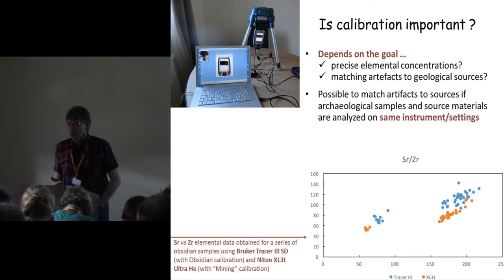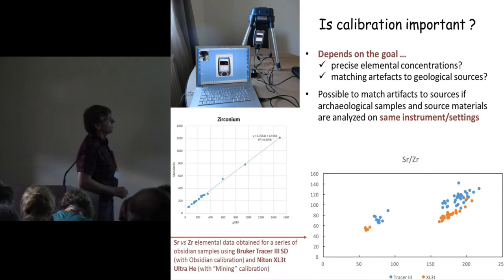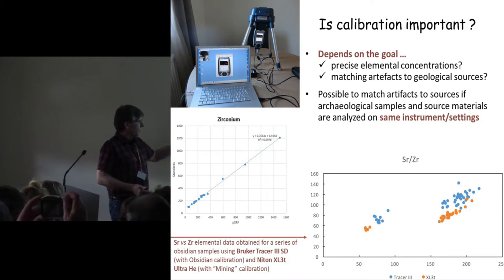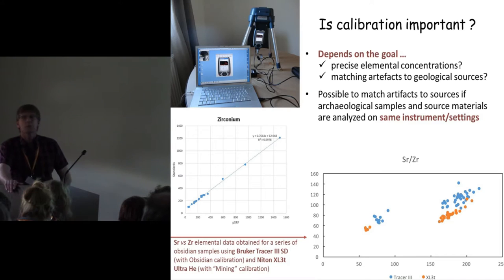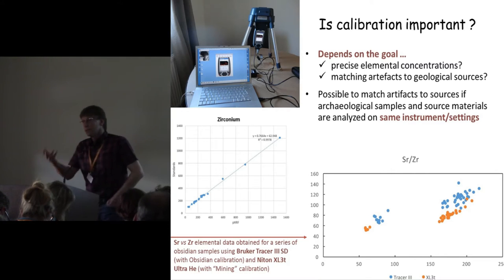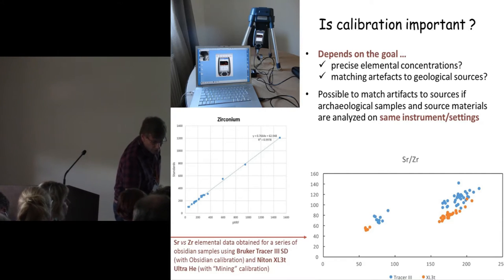It's still showing you two groups. And it's very easy to do the calibrations — it's basically regression analysis. You take a series of measurements on geological reference samples, about 25 or so, measure them with your instrument, and compare the measurements against the known values. By regression analysis, you derive a calibration factor that you can apply to convert the instrument's measurements into precise elemental concentrations.